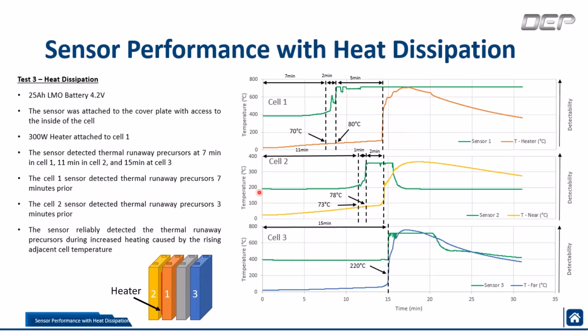Now in cell 2, it wasn't getting directly heated from the heater, but it was increasing in temperature just the same. And it took about 11 minutes for this one to increase in temperature and start degrading from inside the cell. So it reached around 73 degrees before the cell started degrading inside, and our sensor was detecting those changes happening with the chemistry inside the cell. And 3 minutes after that, the cell also went into thermal runaway.